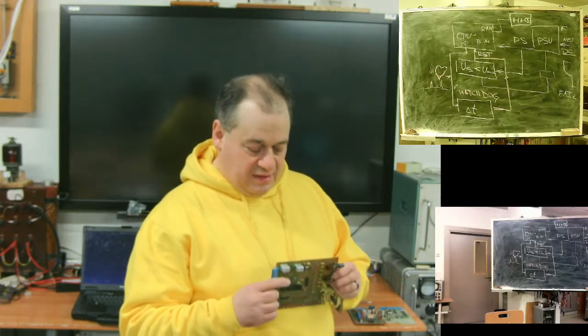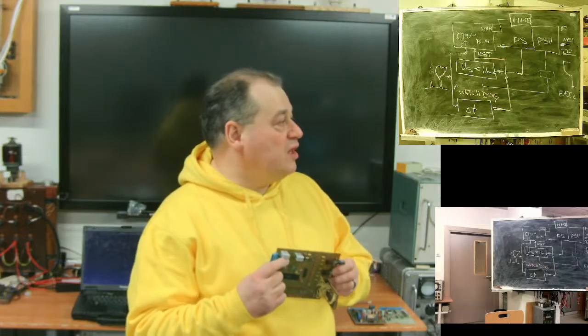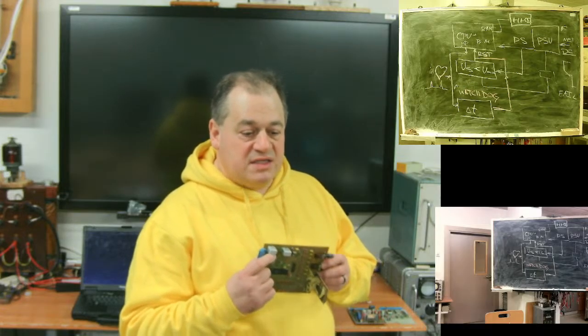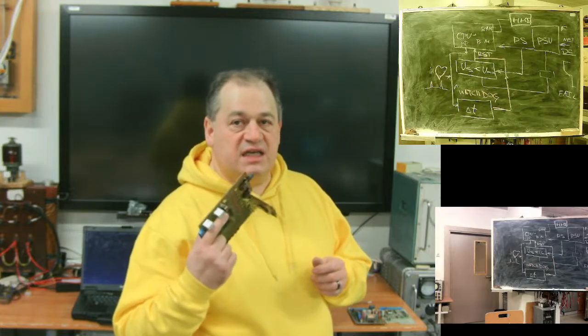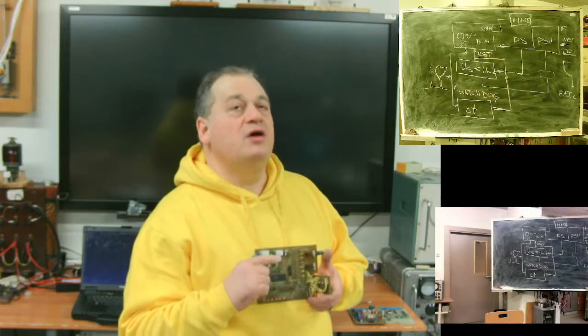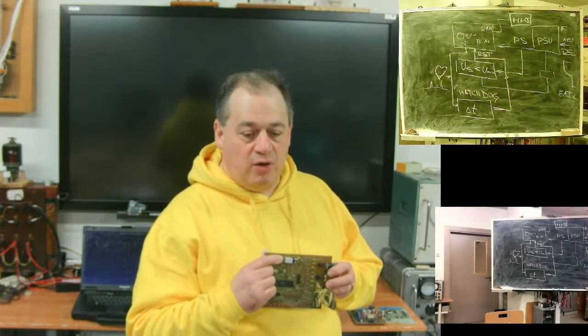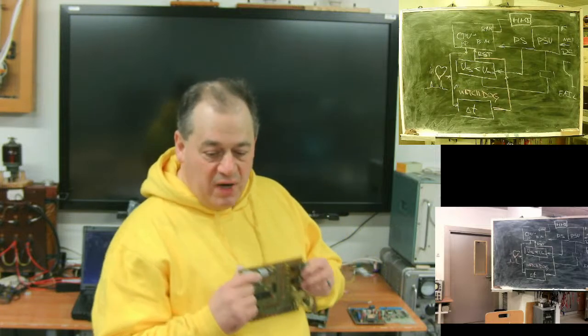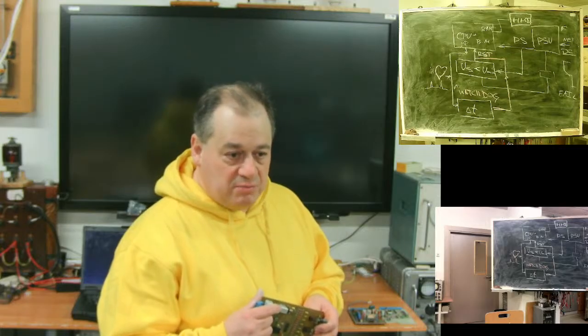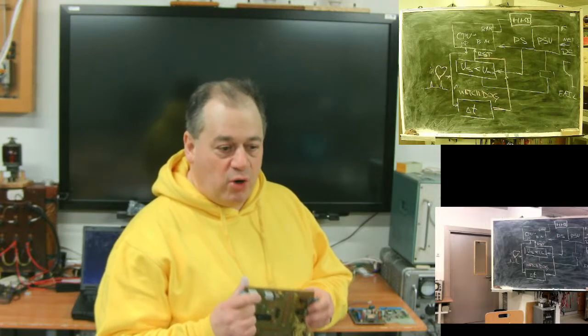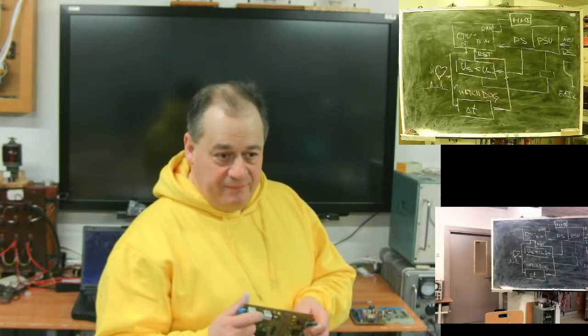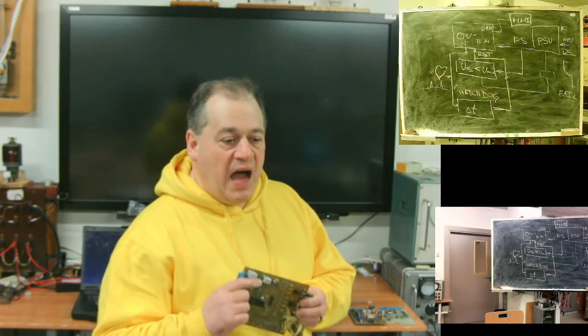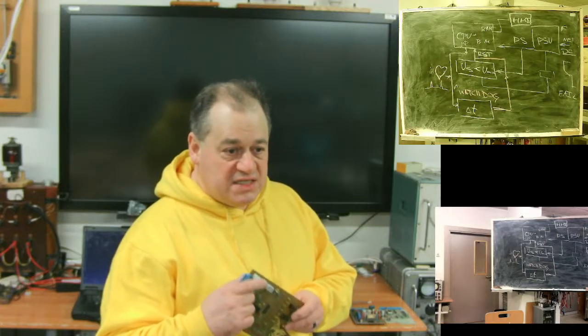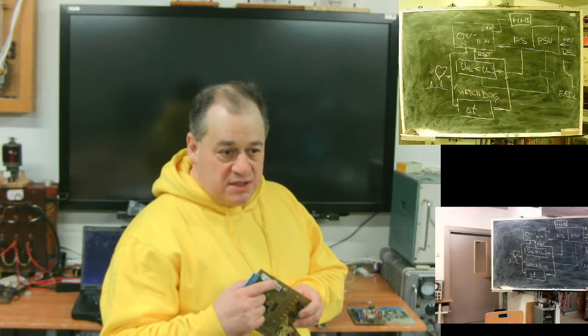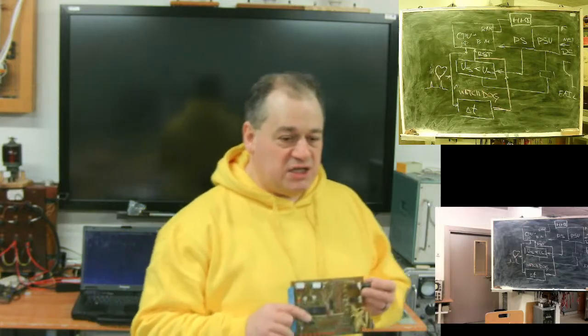Also, it had two relays, to send binary signals. This device does not disconnect anything. It just indicates fault. Anyway, it has a binary signal. I don't know what my customer may think about automation. But if I produce one signal, I'm okay, they can always attach it to some kind of alarm, something not okay. It's for the customer. And the second one, I have something to tell. Binary signal, device operated. This means, please, take attention. I have something for you.